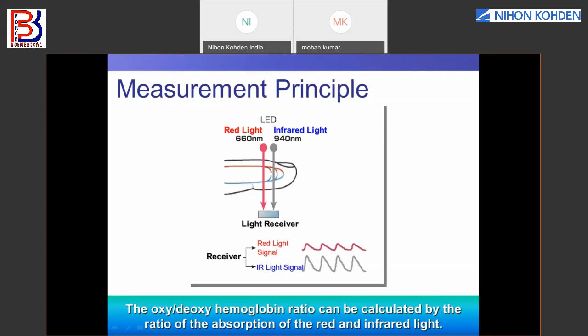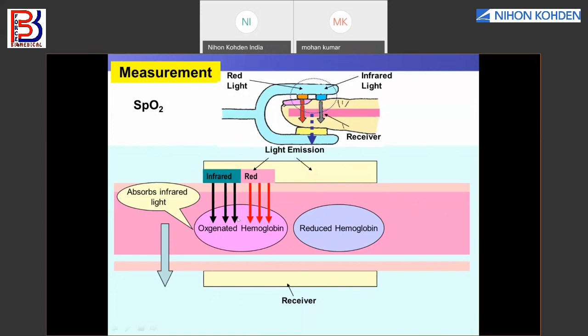So the measurement principle is like this. Oxygenated hemoglobin, which carries more oxygen, absorbs infrared light, whereas the red light passes through. Whereas reduced hemoglobin absorbs the red light, and the infrared light passes through. So based on the absorption of the infrared and red light, the SpO2 values are calculated.